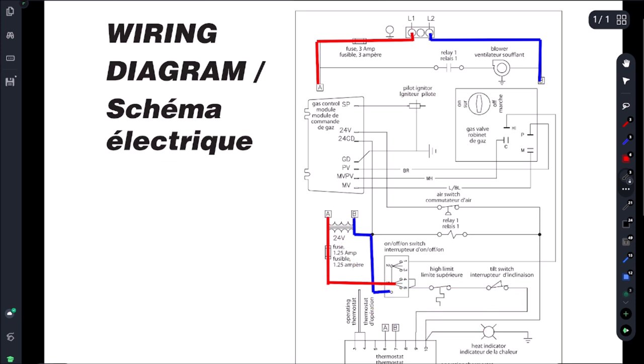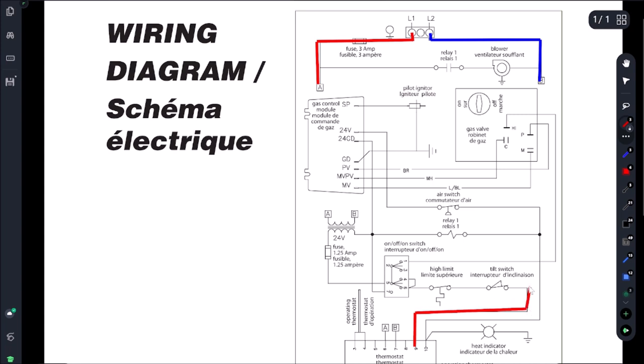So the main problem I see on these units is pin 9 will be hot - so we have power here on pin 9 which is coming through our tilt switch and our limit and it's just a straight shot to the A terminal on the transformer. And then what's happening is this switch doesn't close.